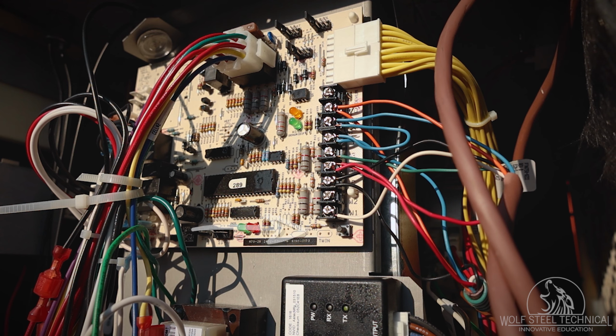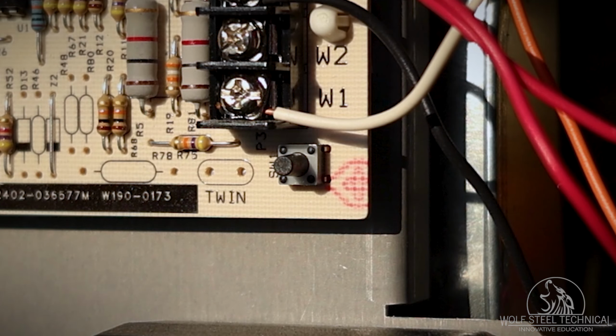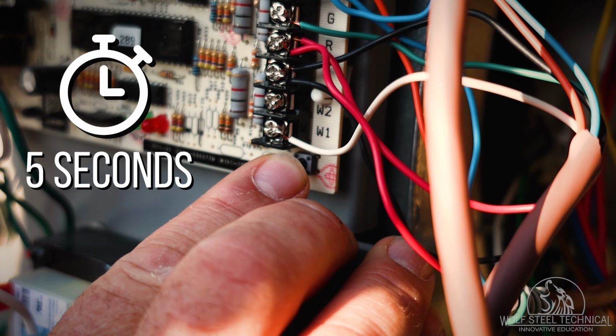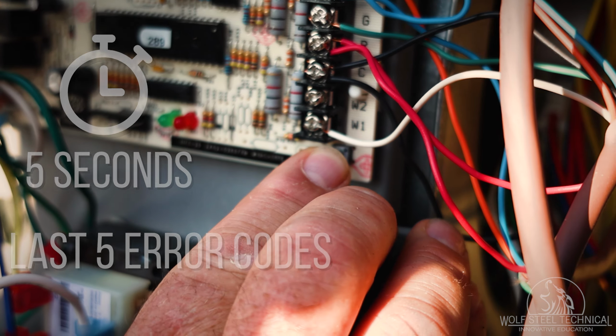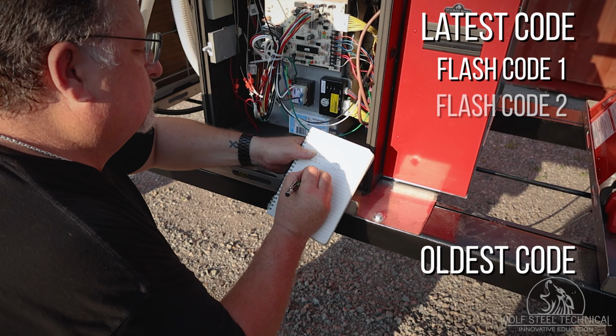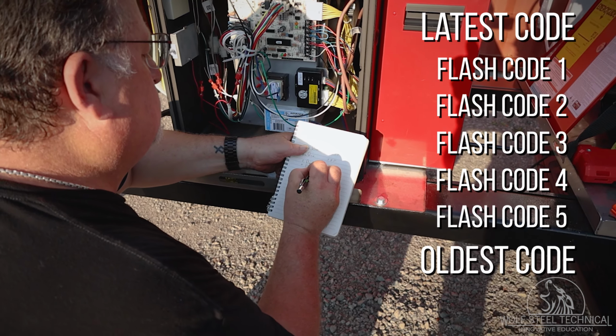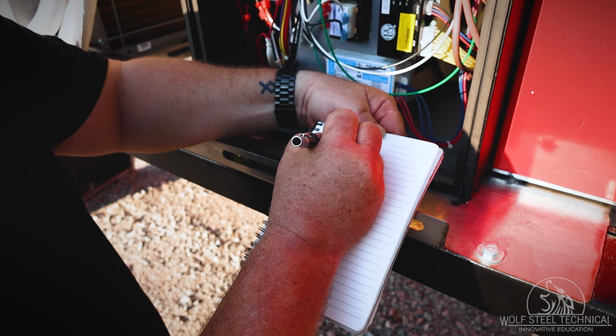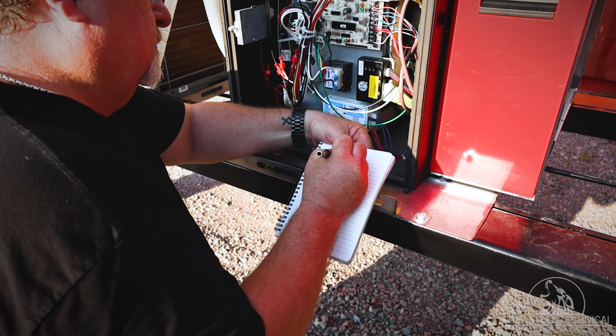Begin by locating the recall button labeled SW1 on the control board next to the stat connections. Press and hold this for 5 seconds to bring up the last 5 error codes. The first flash code that comes up is the latest code, and it will work backwards through the last 5 errors. Service according to the error codes identified in the cache.